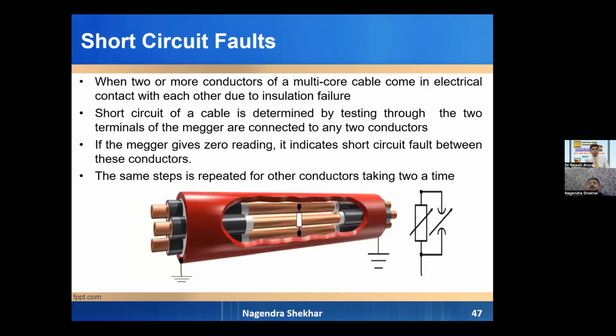A short circuit fault is when any 2 or more phases are short circuited with each other, and in such a condition an earth fault may also be there when this short is also grounded. But in many cases these are phase to phase faults, and it is not necessary that this fault is converted into a ground fault also. So it can be tested by connecting a megger from phase to phase one by one.